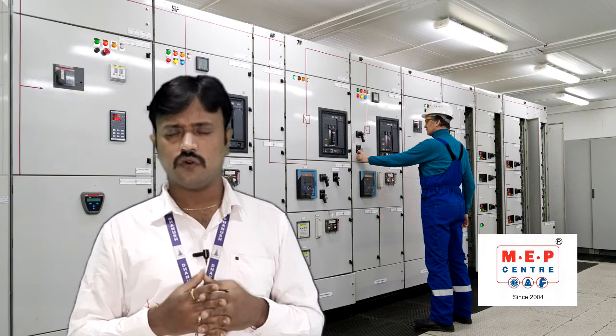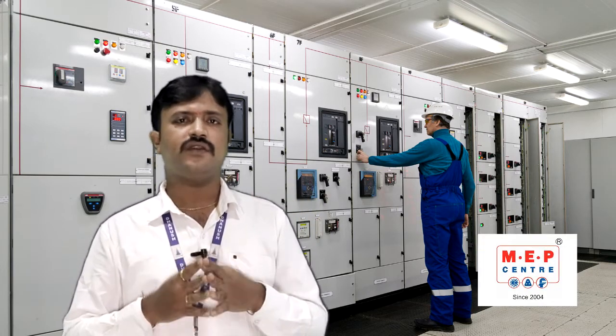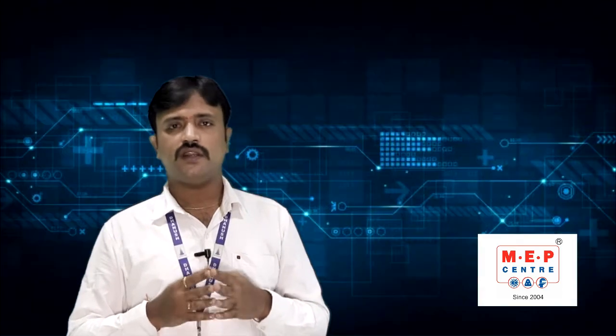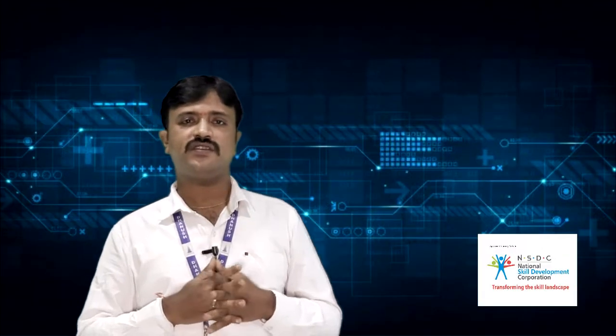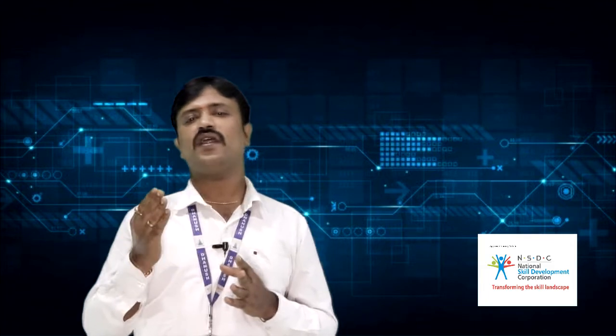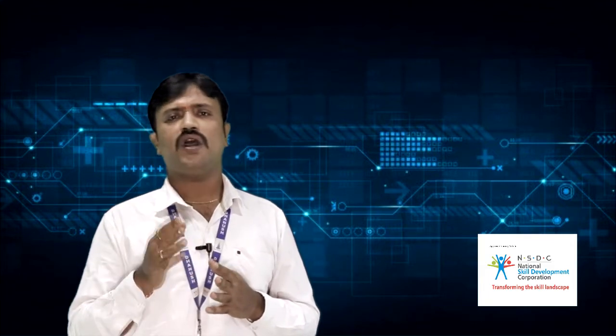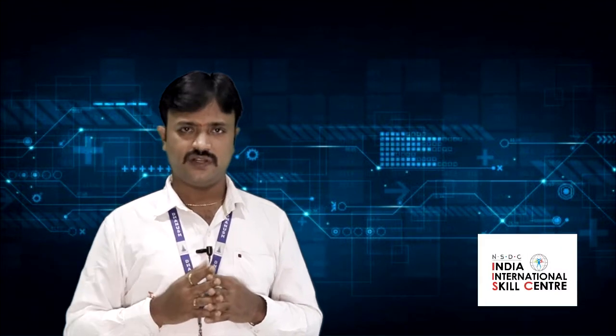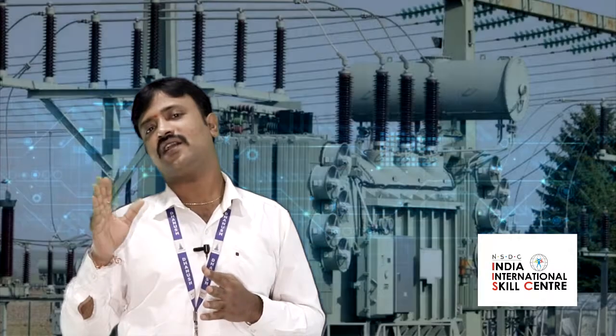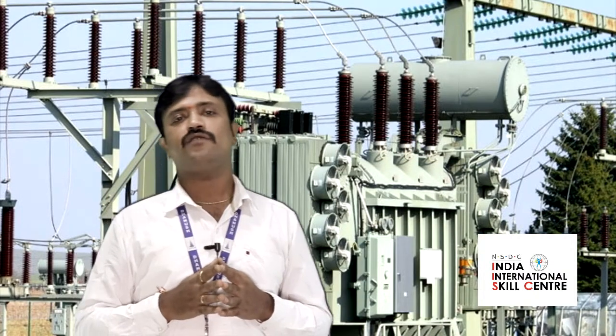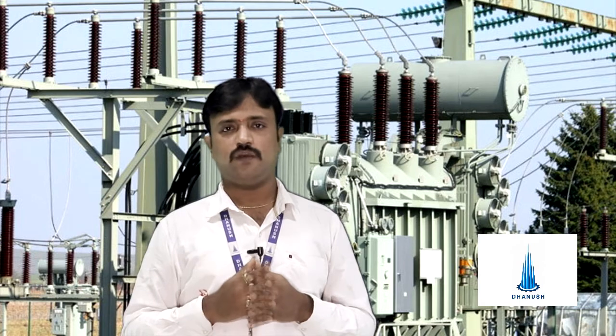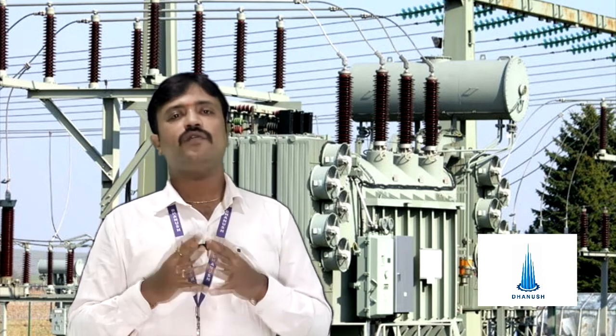Now, once you get the MDB load, we need to decide from where to take the supply for your building. So generally, when you look at the norms of TSPDCL, if your building load is more than 50 kilowatt or 60 kilowatt, you can't take the power from the existing transmission line. So what we do is put a separate transformer for the building. Now we need to define what size of transformer we require. Okay. So how do we define the transformer?